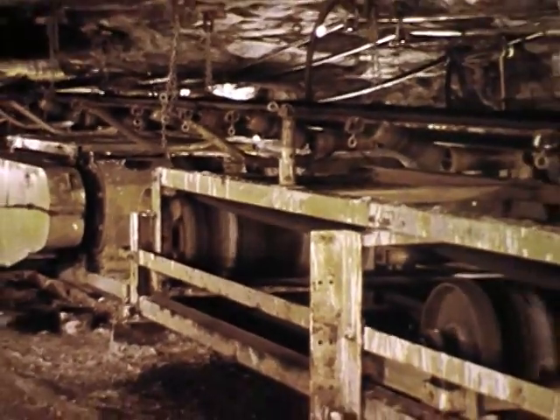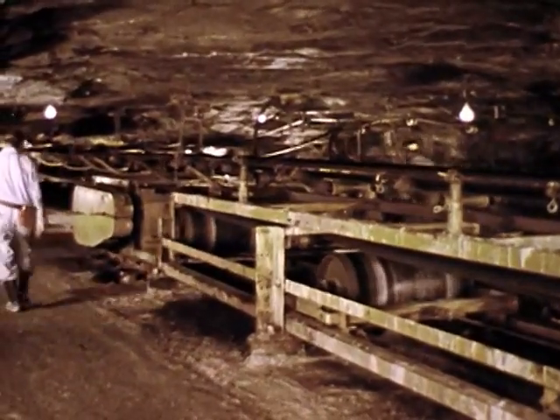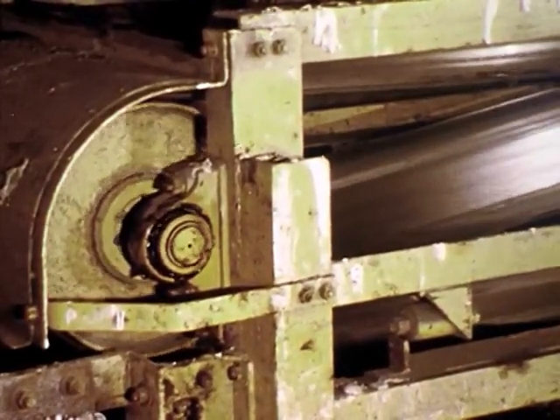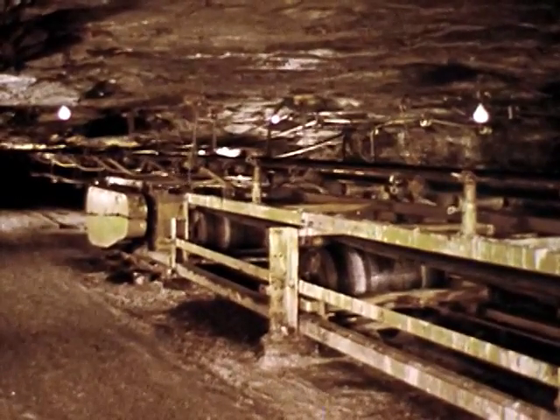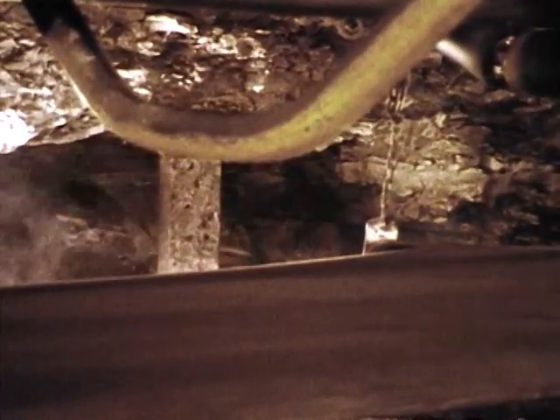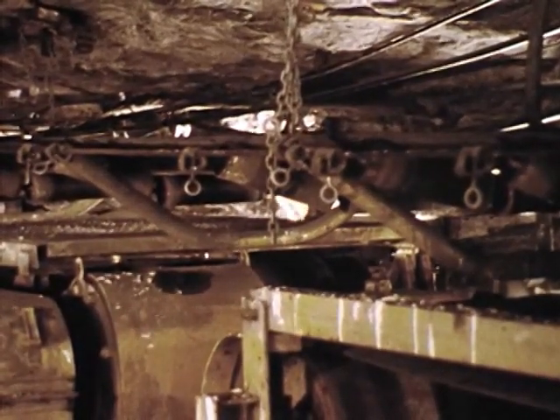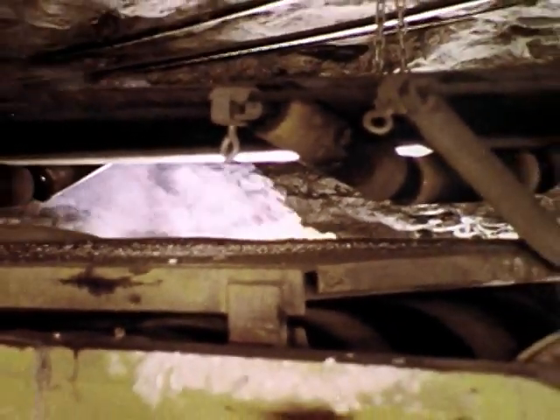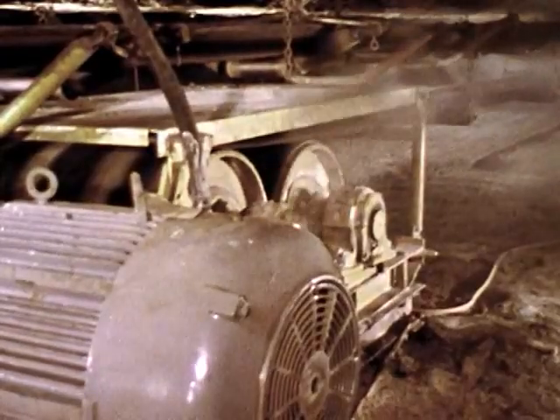Conveyor belt fires, especially in underground installations, greatly endanger life and property. Numerous belt fires have broken out during off-shift periods after belts have been shut down. A common source of conveyor belt fires is heat developed from electrical defects in the driving mechanism, which is transmitted to the belt. Also, heat from friction can develop at drive or tail pulleys and at frozen trough or return idlers. Once started, a fire involving a flammable belt usually spreads rapidly. The combustion produces high temperature and dense, highly toxic smoke.